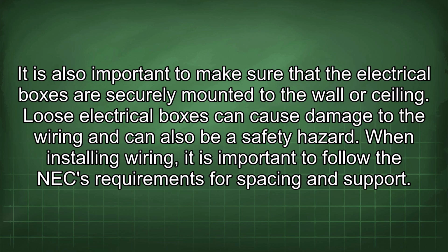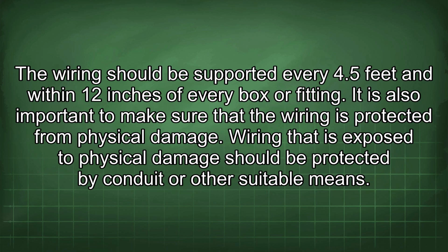When installing wiring, it is important to follow the NEC requirements for spacing and support. The wiring should be supported every 4.5 feet and within 12 inches of every box or fitting. It is also important to make sure that the wiring is protected from physical damage. Wiring that is exposed to physical damage should be protected by conduit or other suitable means.